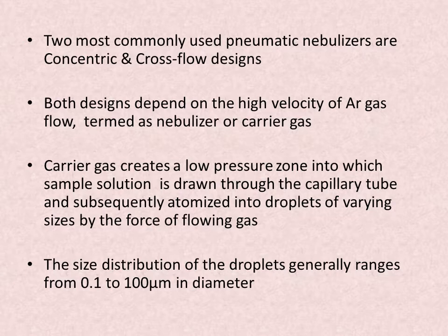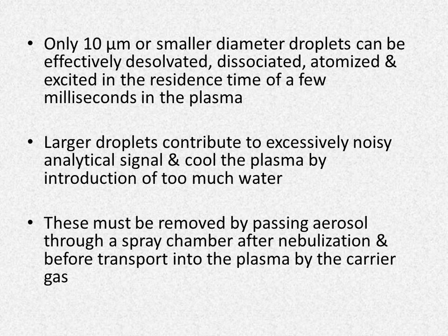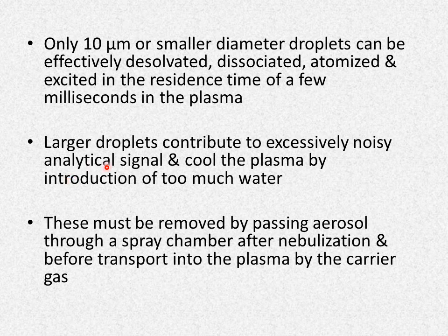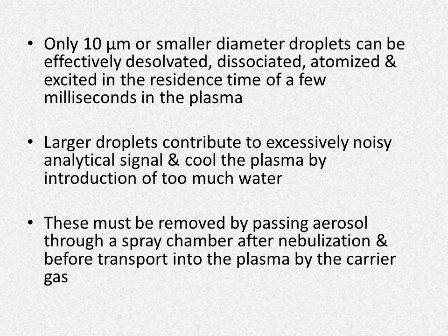The droplets produced are of different sizes, and the size distribution generally ranges from 0.1 to 100 micrometers in diameter. However, only droplets of 10 micrometers or smaller diameter can be effectively desolvated, dissociated, atomized, and excited within the residence time of a few milliseconds in the plasma. Larger droplets contribute to an excessively noisy analytical signal and cool the plasma by introducing too much water, so they are problematic and must be removed.